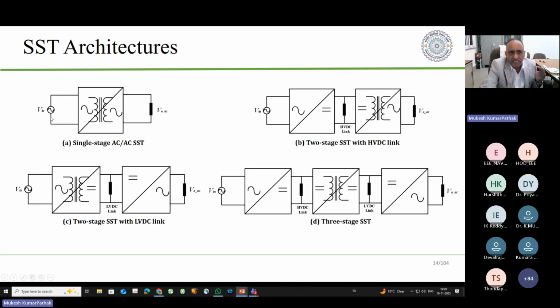So if it's possible to convert this AC directly into an AC of 50 Hz with a solid state, high frequency transformer link, it would be a single stage AC to AC SST. That means here the low frequency or power frequency input is converted into high frequency, and then that high frequency is applied to the transformer, and the next stage would convert this to AC at power frequency.